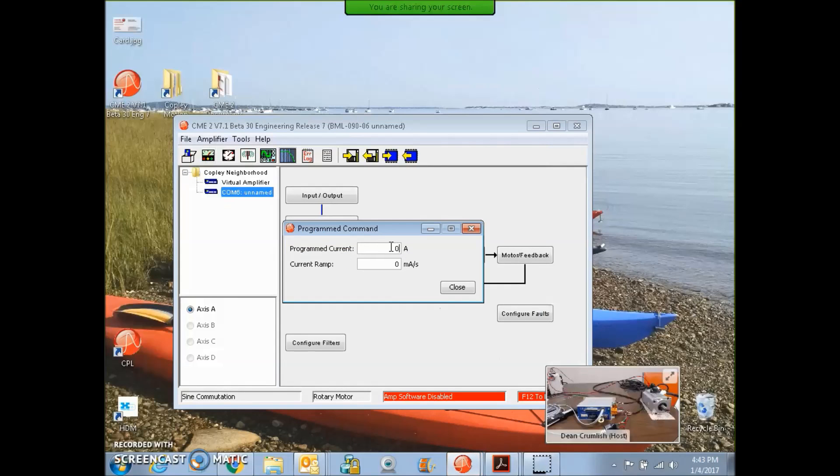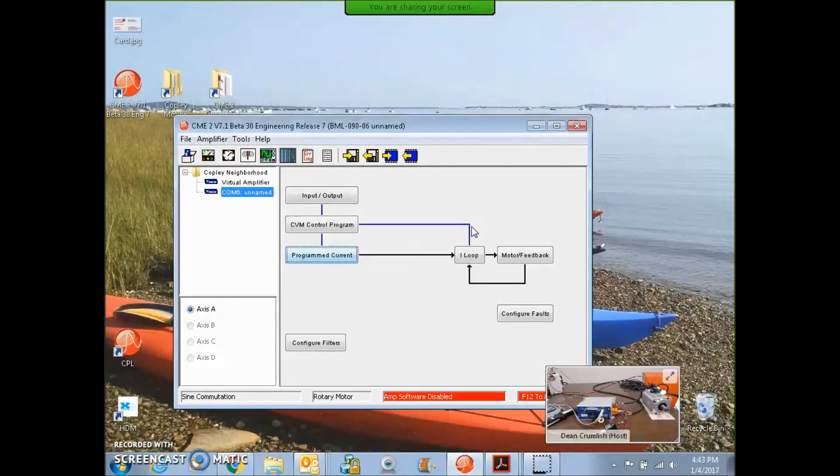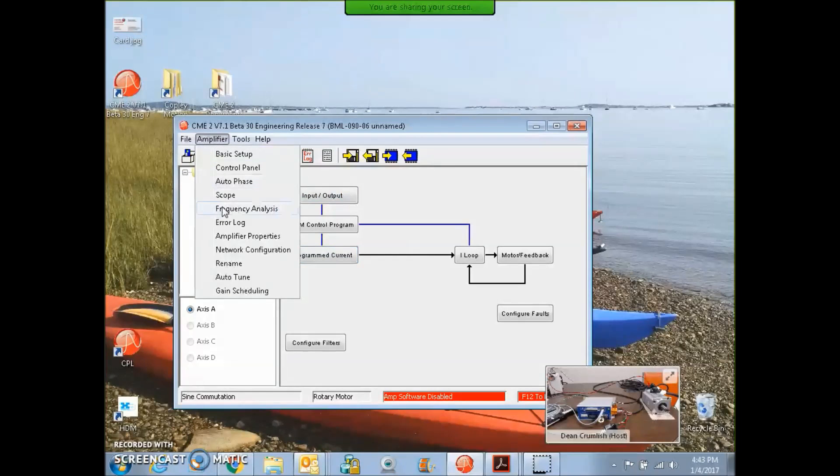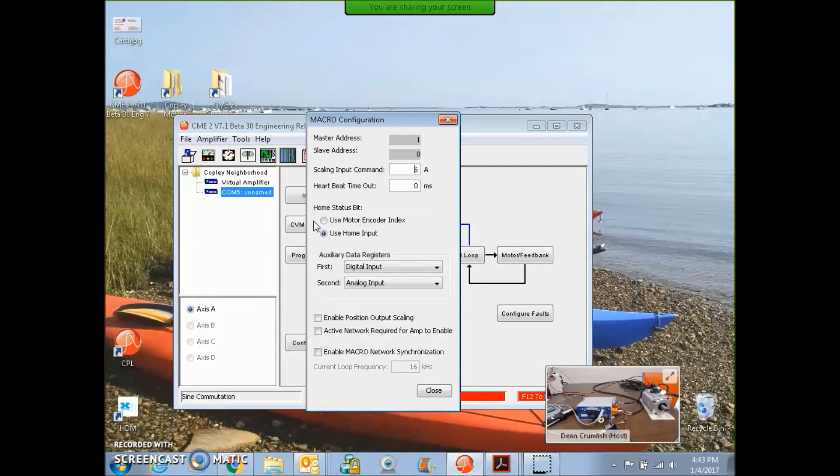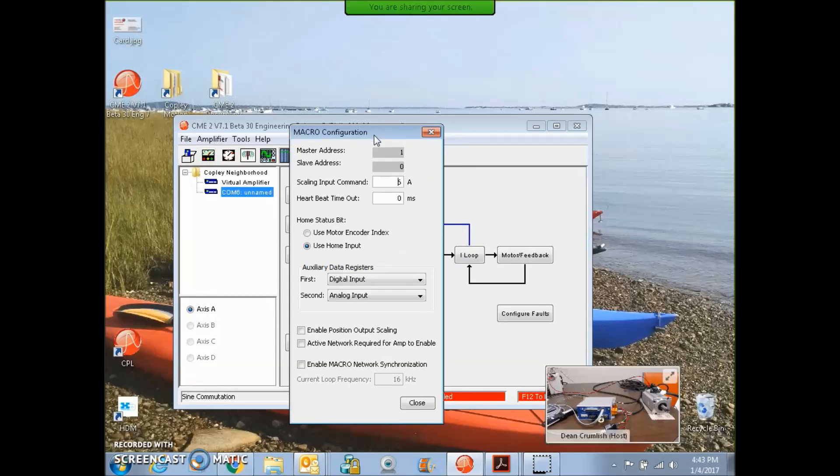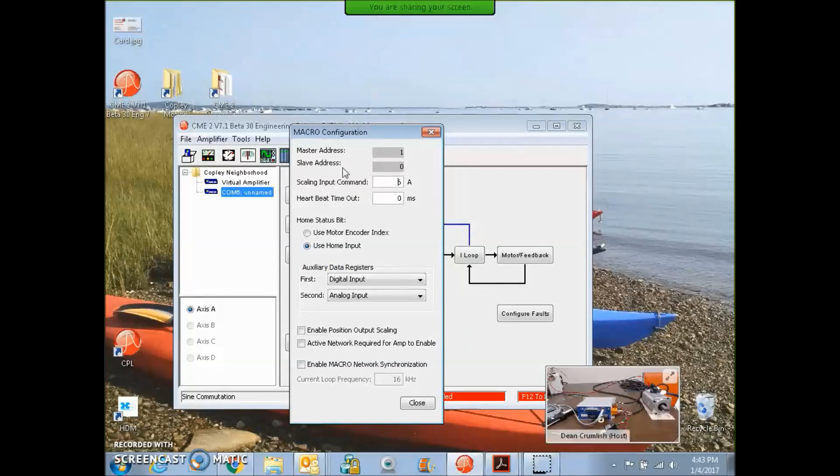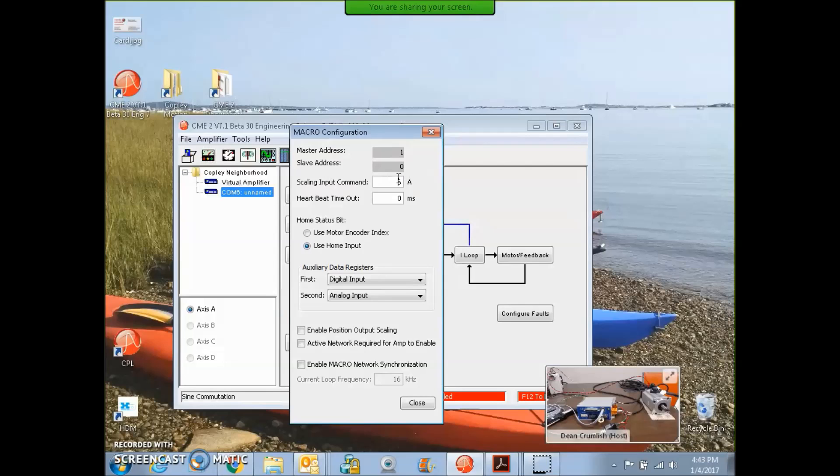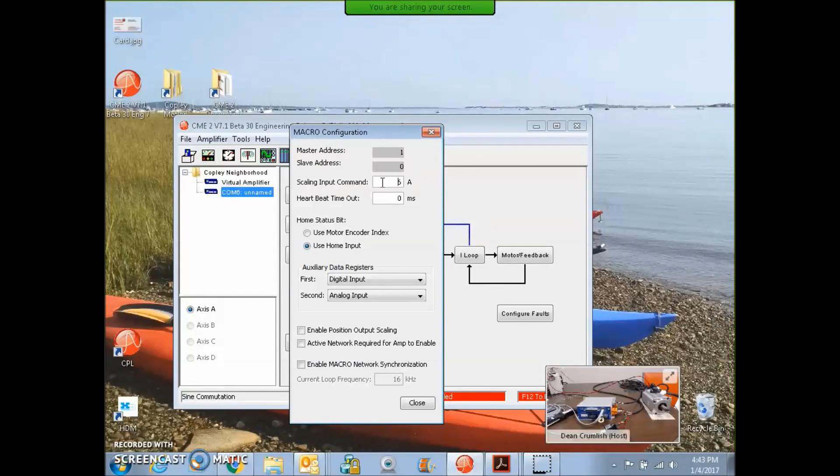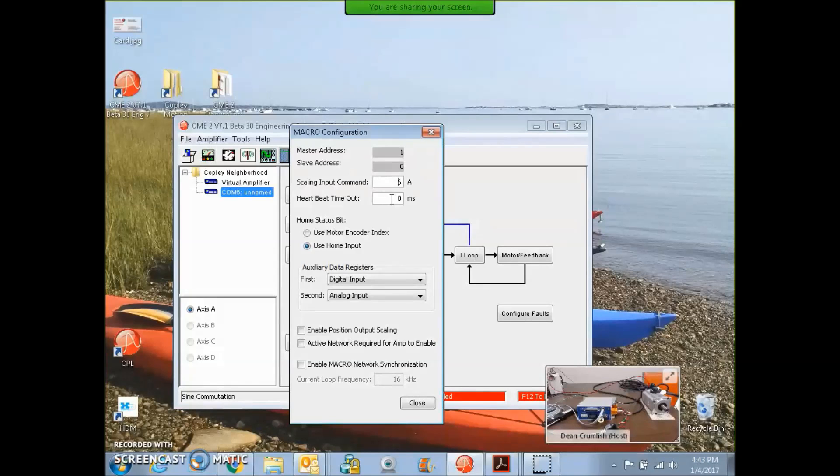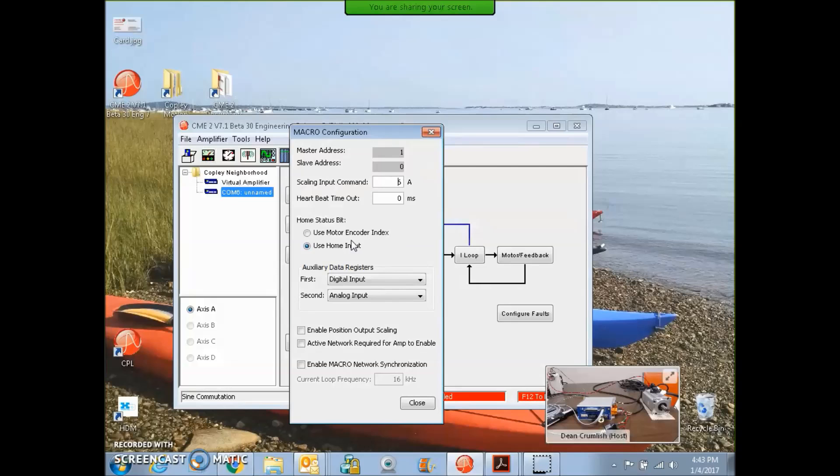From the amplifier network configuration screen, we can see that we were prepared for the macro master to come in. The master address was set to one with a switch. The slave address here is set to zero, but there's other positions you could put it in. The scaling input command is six amps. There's a heartbeat for timeout to make sure things are connected.